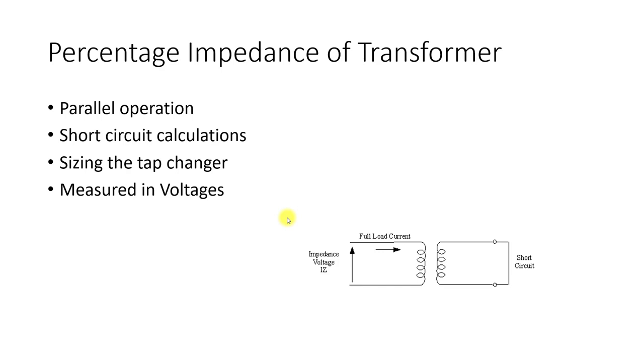Another important aspect of percentage impedance is its relationship to fault current. For short-circuit calculations, if the transformer secondary terminals are dead short-circuited, the fault current depends on the impedance of the transformer — that is, the percentage impedance. The percentage impedance functions to limit the fault current. We can use it to calculate fault MVA, and from the fault MVA we can calculate the fault current or short-circuit current.